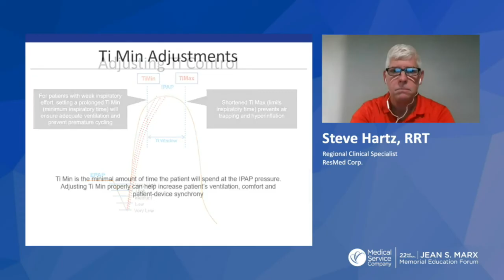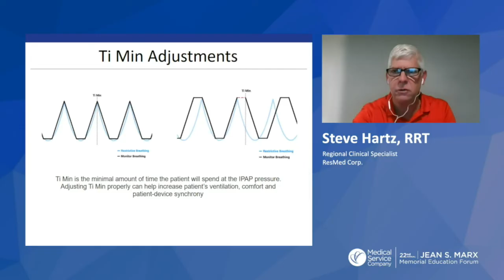TI min adjustments. It's a minimal amount of time. We know that. When we look at the first one, that might be a setting of 0.1. And I'm not going to guess how much it is, but we can extend that breath out, make that waveform bigger. And anything that's underneath those triangles is a bigger breath. So just by adding a few more tenths of a second, maybe a 0.3 to a 0.8 or what have you, is going to help ultimately change that patient's ventilation by adding more tidal volume just with time and minimizing the pressures that are needed.